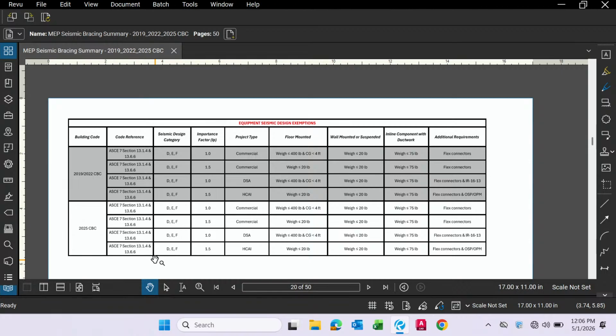Okay. Now, if you have an inline equipment component with ductwork, we're talking about VAV boxes or terminal boxes that are installed in line with the ductwork, that requirement goes up to 75 pounds. So again, 20 pounds for regular suspended equipment, and the cutoff is 75 pounds for inline. Now, if it's a commercial building and your component has an importance factor of 1.5, remember that 400 pounds here. If it has an importance factor of 1.5, that requirement comes after 20 pounds now. So the importance factor plays a big role in where the exemption cutoff is. The 20 pounds for suspended and 75 pounds for inline is still in place, even though it's a 1.5 importance factor.